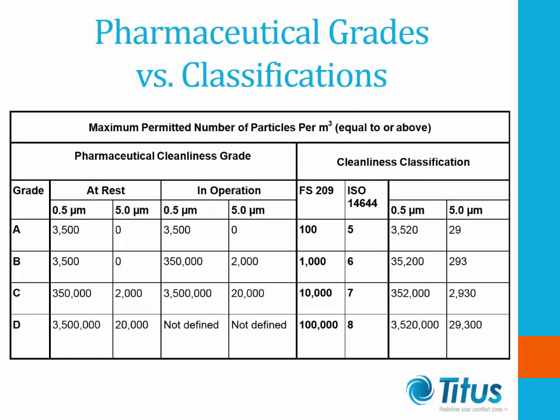For the pharmaceutical industry, there is another classification using grades: Grade A, B, C, and D, defined under two occupancy states — at-rest and in-operation. Typically, Grade A is considered equivalent to ISO 5, B to ISO 6, C to ISO 7, and D to ISO 8. However, if we look at total particle counts at 0.5 or 5.0 microns, the allowed counts may not be fully identical, so these classifications are not truly equivalent.